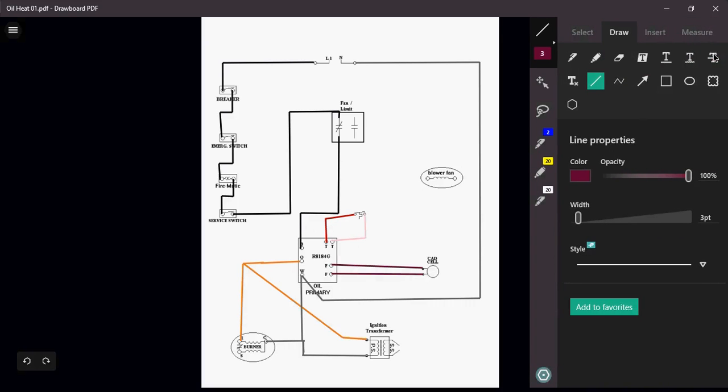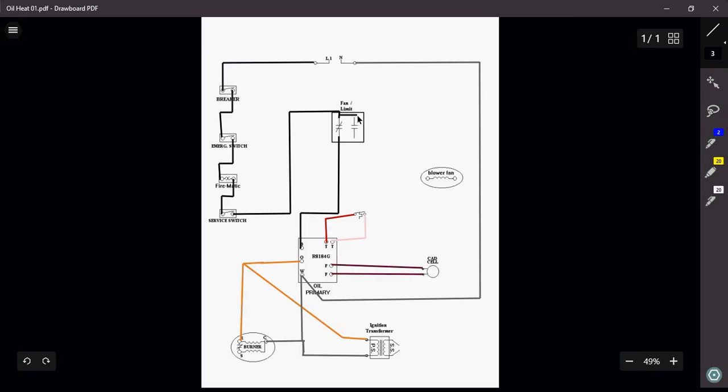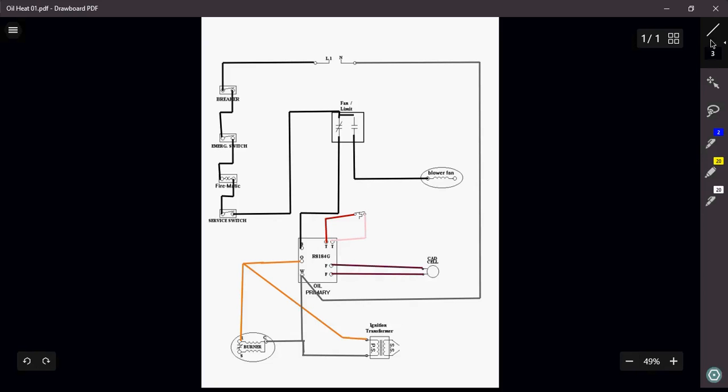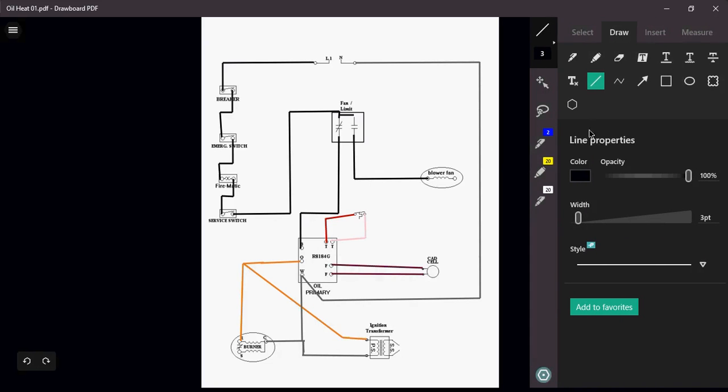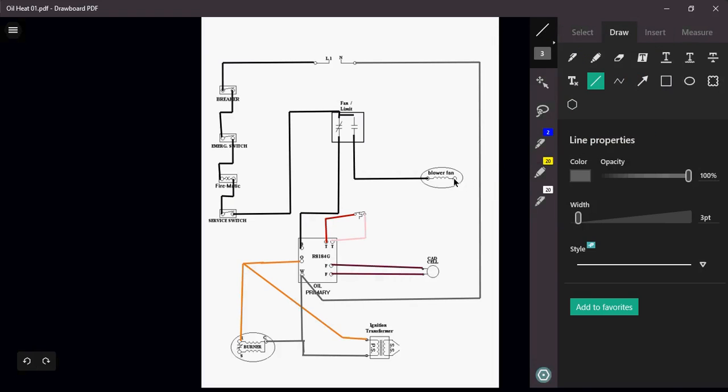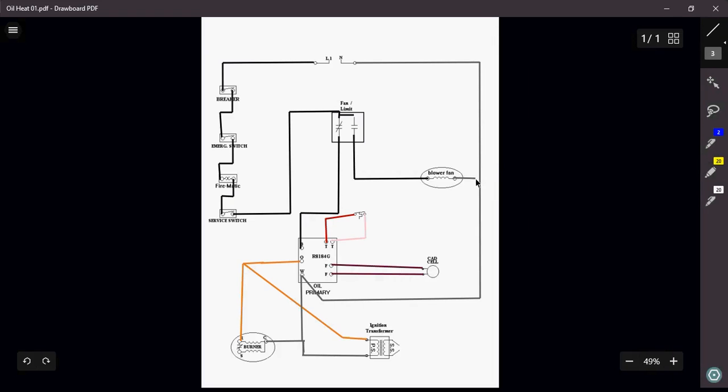So, out of my fan limit switch, I want to power up my other side of my control device here. Remember, this is my temperature-actuated switch that's going to close once my furnace reaches about 140, maybe about 150 degrees. That switch will now close, and it is now going to send power to my blower. And in turn, my blower will turn on. And that just completes that circuit.